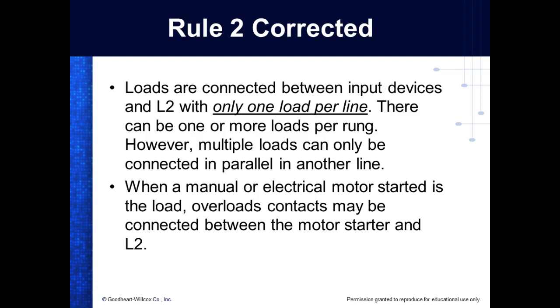and L2. We have a problem with motors and overcurrent protection devices. So an overcurrent protection device, like a circuit breaker or like a fuse, is set to blow at a certain current, or pop or blow, whatever you want to call it. The problem we have with motors is when they stall or when they start, they pull between 6 to 8 times the run current at the instant they start.